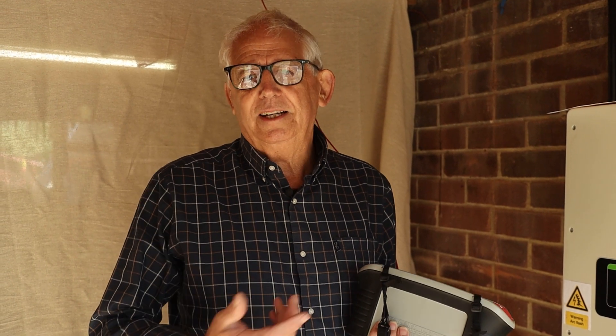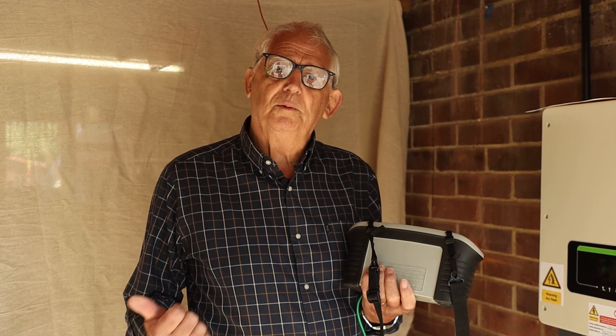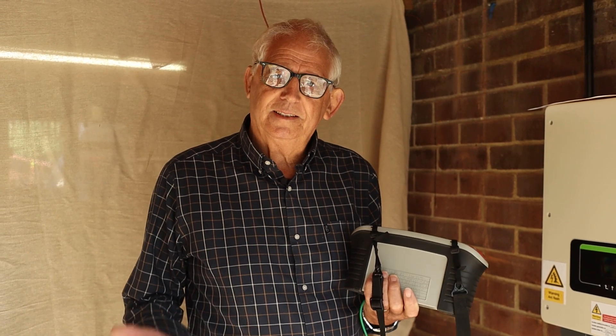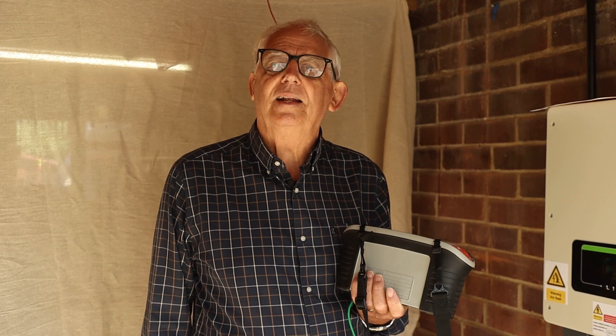You could argue — can you touch it from a Velux window? Even if you can touch it from a Velux window, it's still just a piece of metal, so there's still no need to bond it at all. If it was on a metal roof, the story might be a little bit different, and I'm going to do a video about that a little bit later. There you go.